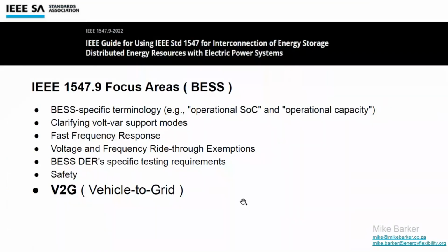Okay, interconnection of energy storage, or a BESS. The focus here, again, is to define the terminology: state of charge - what does it mean? Operational capacity. Clearly, if your inverter has a battery behind it, it can play a very important part in terms of volt-var support, volt power. You've got the battery there, and it's always there, unlike solar or wind, which might not be there on the day.